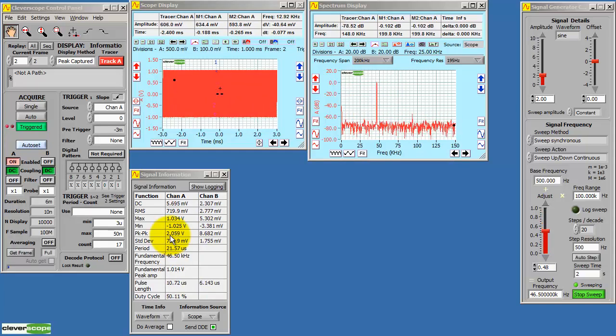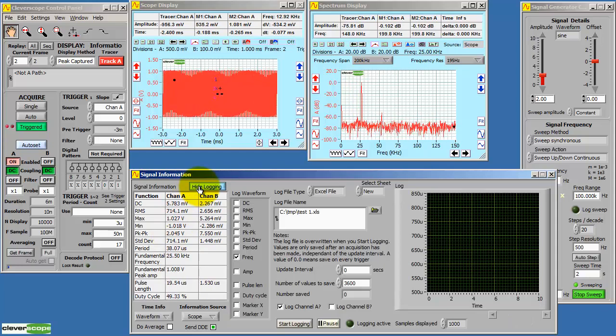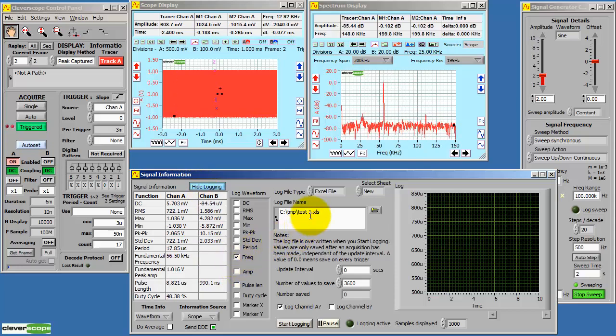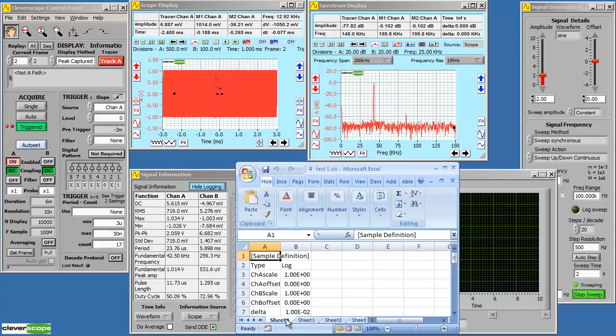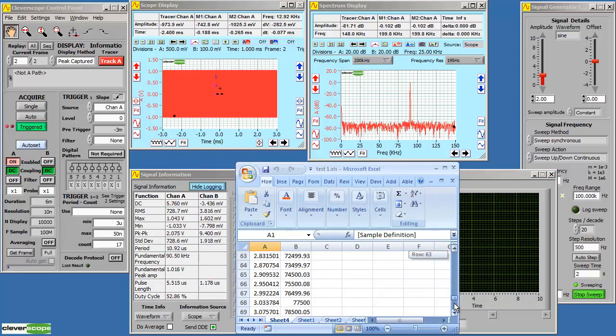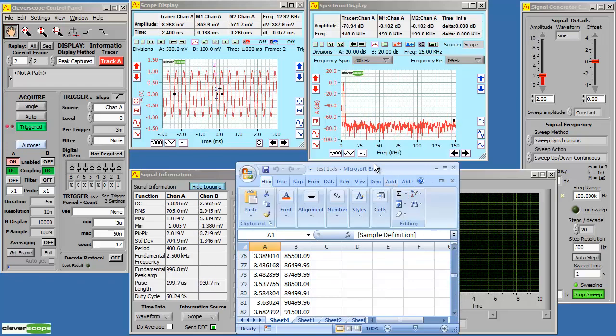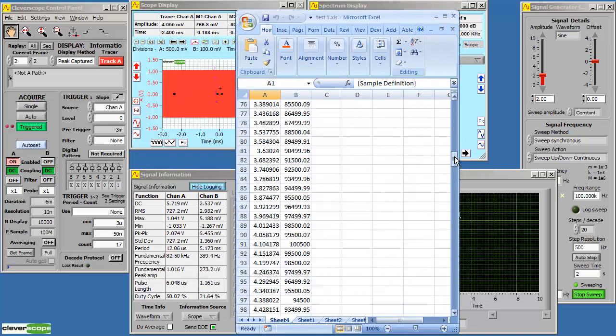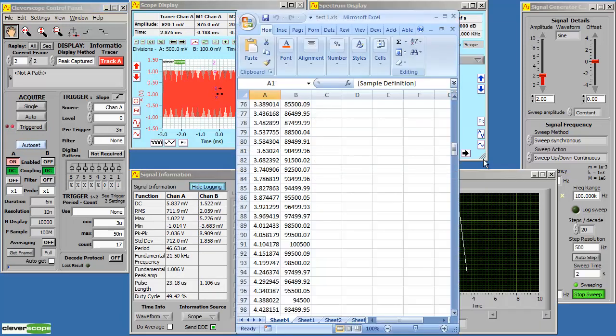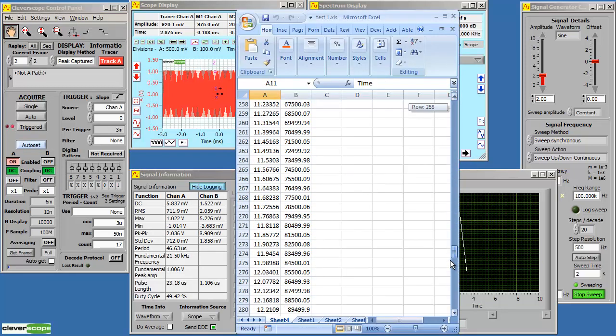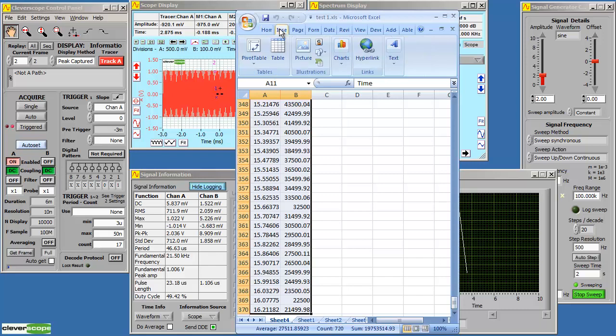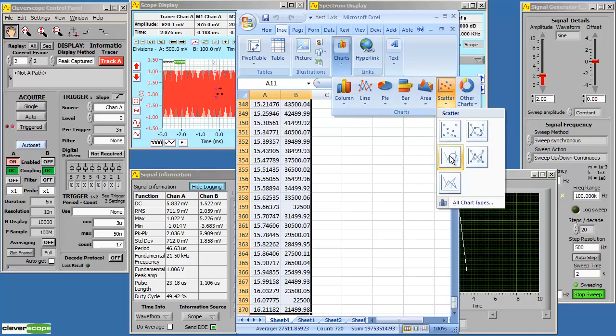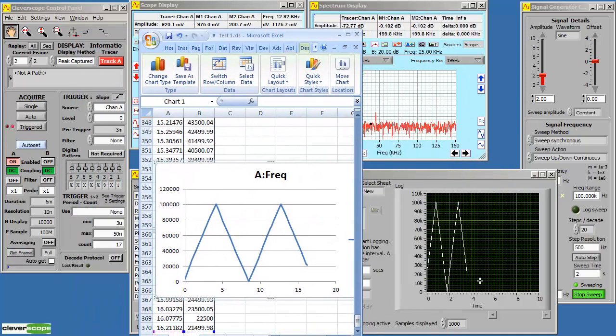The signal information can also do logging. Click show logging. And we can log into an Excel file or into a text file. Here I'm choosing to log frequency into an Excel file. I'll start logging. It brings up the Excel file and it starts logging to it. Once we've finished, we can then use the Excel file for our own purposes. For example, we could make a graph within the Excel. There we are. As you can see, this is very similar to the one that we recorded ourselves.